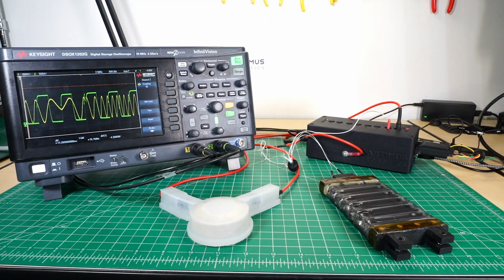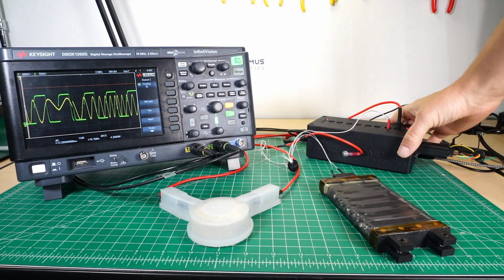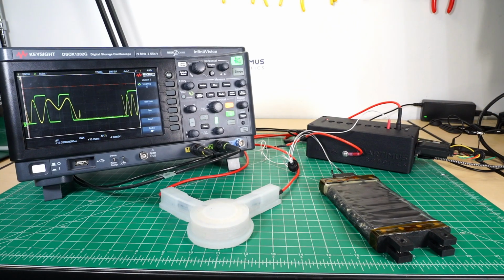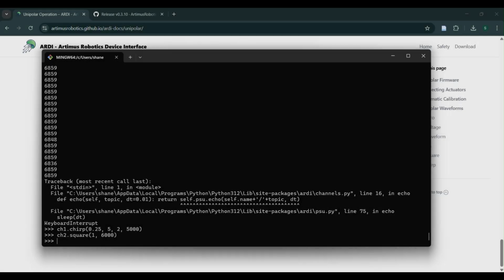These waveforms will run indefinitely unless programmed otherwise. I can stop the amplifier by toggling the high voltage switch to the off position. This will immediately discharge all of the output channels. I can also use ARDI to set the output voltages to 0.